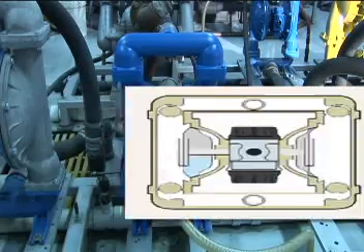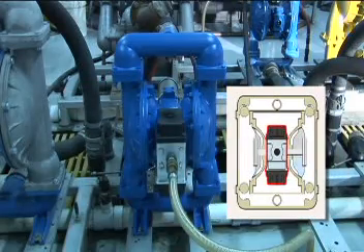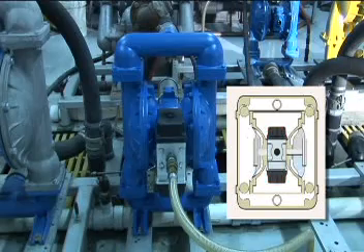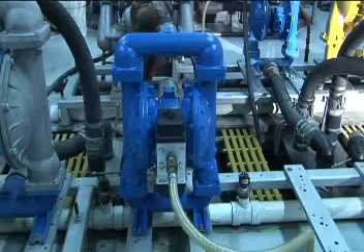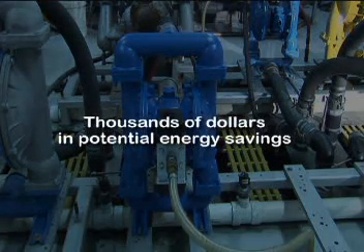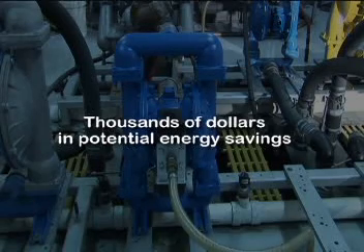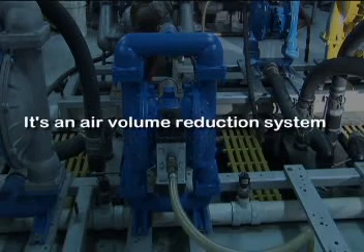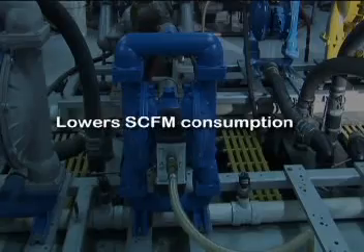Here's how it works. With AirVantage energy-saving technology, your pump remains the steady workhorse it's always been, but now it's much more efficient. Tests show that AODD pumps can operate with reduced air volume while sustaining the desired fluid flow. This means that air distributed to the diaphragm can be reduced, resulting in thousands of dollars in potential energy savings. That's what AirVantage is all about — it's an air volume reduction system that reduces energy costs by up to 50% over conventional AODD pumps by lowering SCFM consumption.